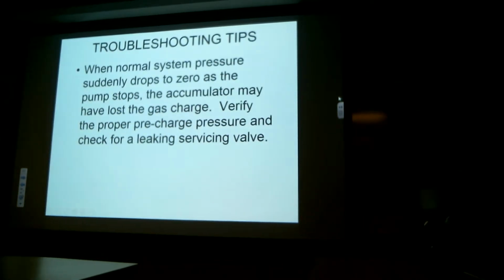It says when normal system pressure suddenly drops to 0 as the pump stops, the accumulator may have lost the gas charge. Verify the proper pre-charge pressure and check for a leaking service valve. We can check for a leaking service valve easily. If you're looking for a leak of the service valve, soapy water will do the trick. If you see bubbles coming from the service valve, usually that indicates that the gas charge is leaking out of it. Might be the gasket on the service valve, might be the valve itself, or might be not torqued correctly, but it's leaking gas.